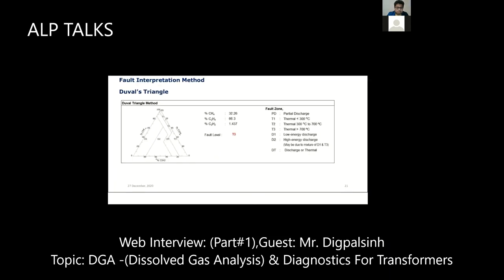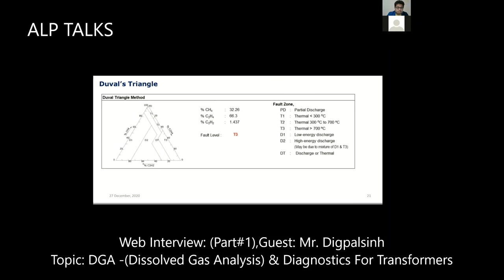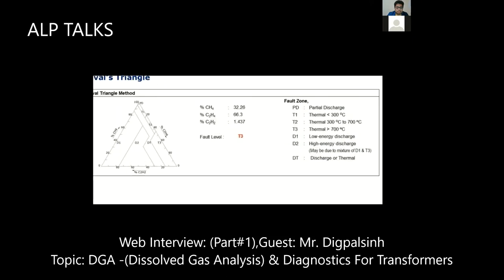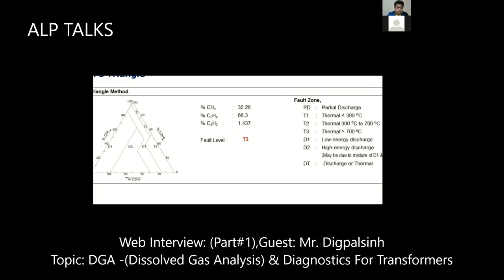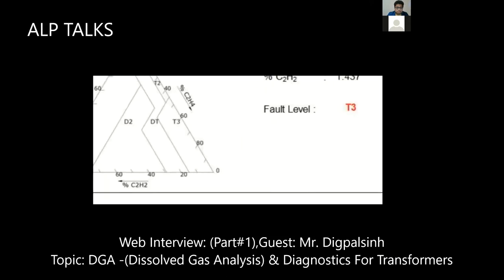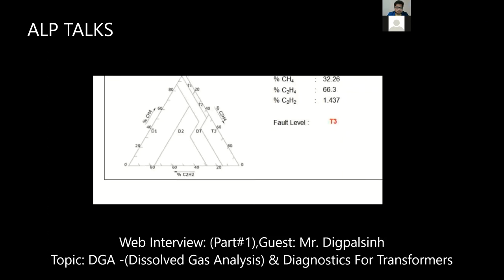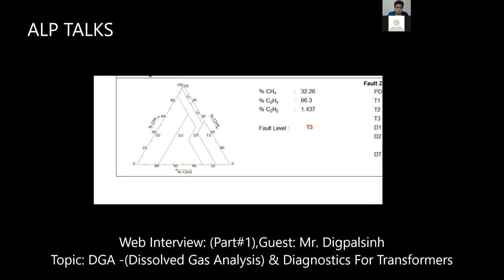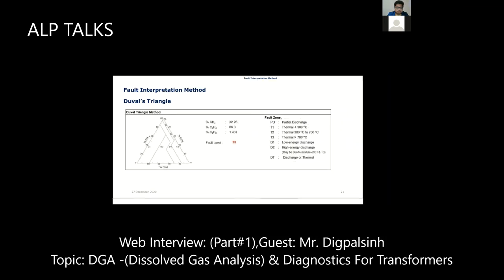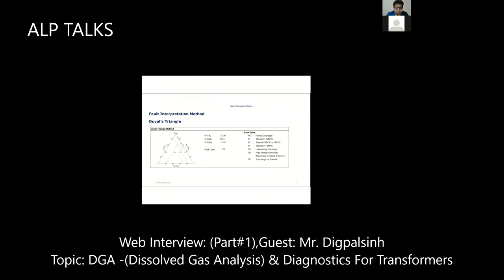This is the Duval's triangle example. The fault zones are the same as we discussed in the abbreviation section. I took random numbers of CH4, C2H4 (ethylene), and C2H2 acetylene, and calculated the percentages. This percentage lies in the T3 section, so I found the fault level is T3, which is a thermal fault greater than 700 degrees Celsius. So that's it for the interpretation method.